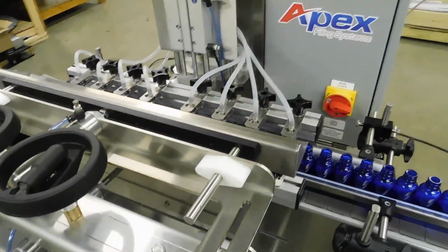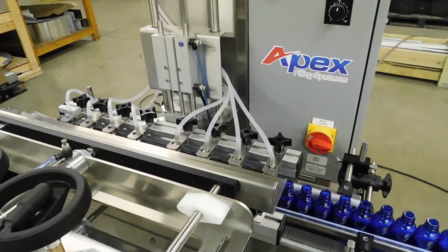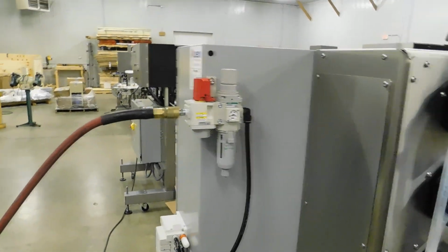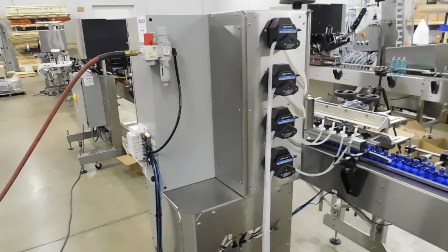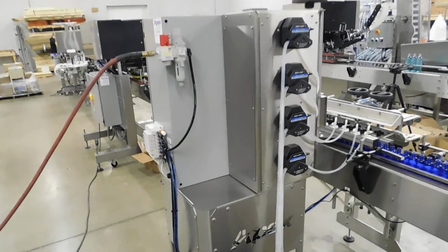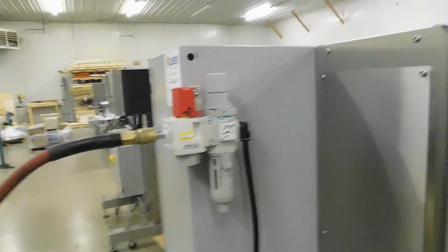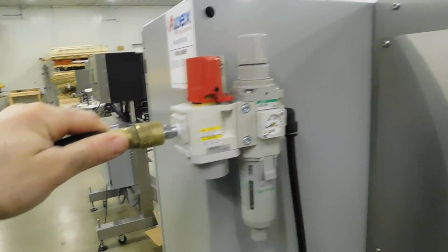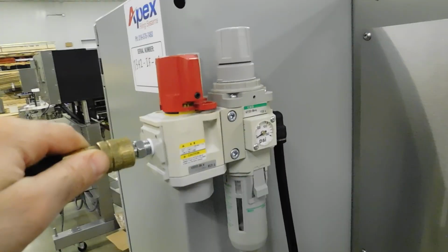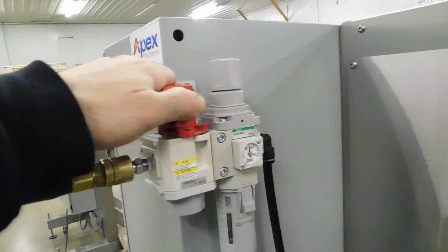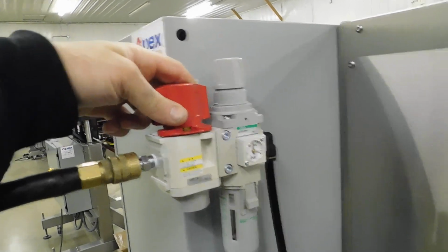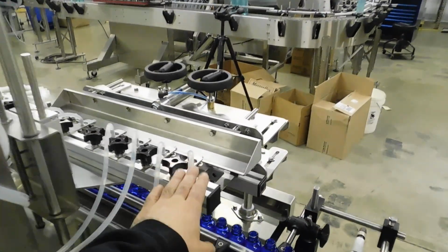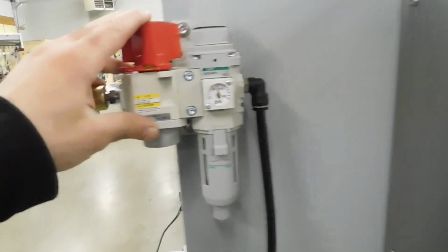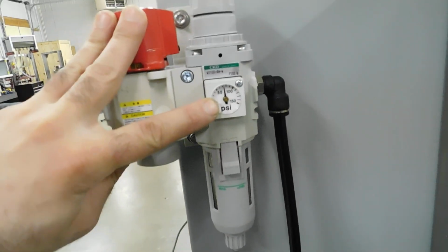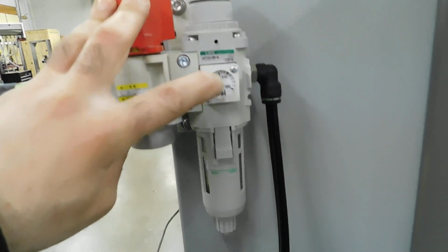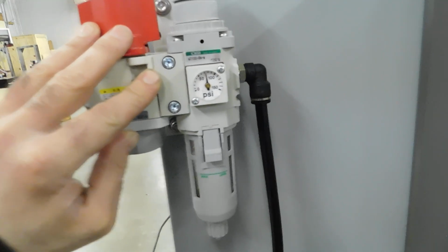We can now turn on the air and power to the machine. The air is located on the back side of the peristaltic filling machine. Connect your air here and turn your red knob clockwise, and that will lift your fill head bar up. You should see pressure displayed on your gauge. Usually anywhere from 60 to 90 psi is a good range.